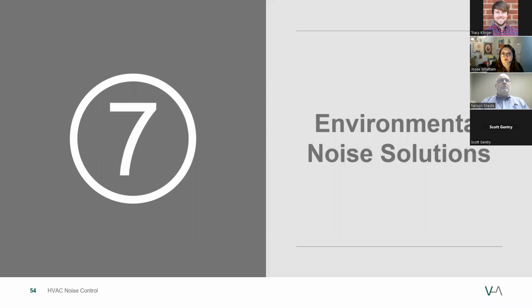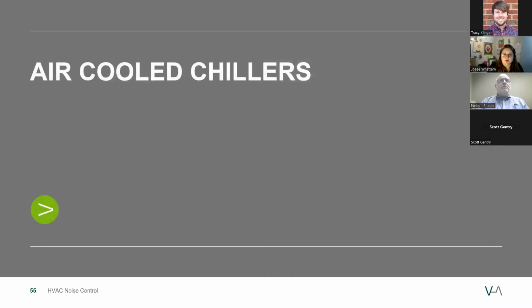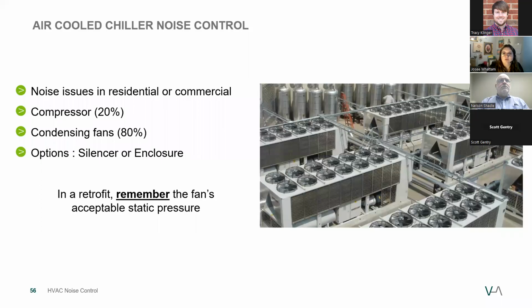So that leads us to exploring a few environmental noise solutions, starting with air-cooled chillers. Air-cooled chillers pose potential noise issues at the property line in residential and commercial applications. Approximately 20% of the noise generated comes from the compressor. The remaining 80% of generated noise comes from the condensing fans. Good options for noise control are inlet and outlet silencers or an acoustical enclosure. To determine the right solution in a retrofit, something to consider is the amount of static pressure the fans can take.